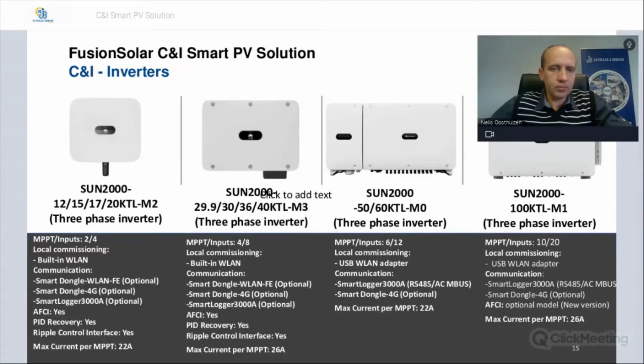And then moving over to the next section, the mid-range of the C&I would be from the 29.9 or 30 kTL all the way to a 40 kTL. Main difference between this one and the smaller one is that it's got two more MPPTs with two inputs each, so you can now have a total of 8 strings connected to it. Maximum current per MPPT would be 26 amps, which means that this inverter is suitable with modern high-powered PV modules.